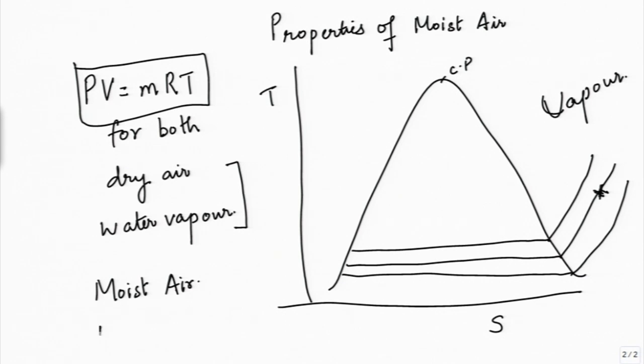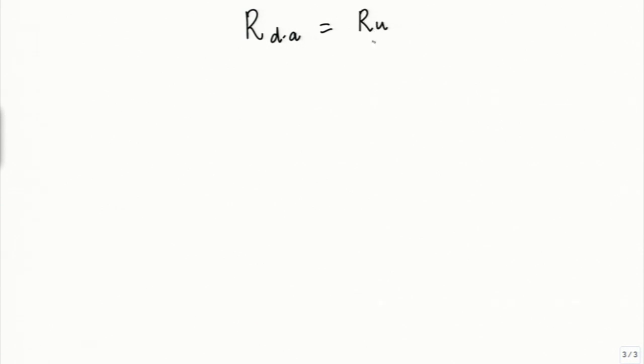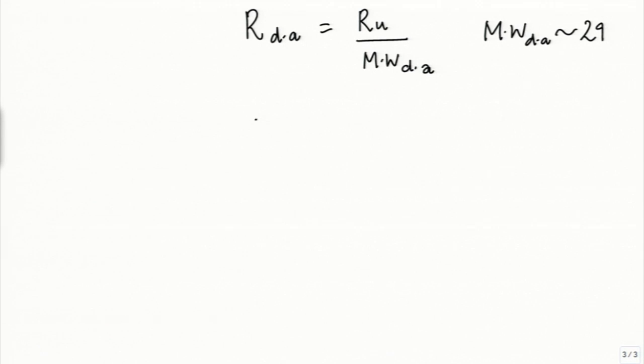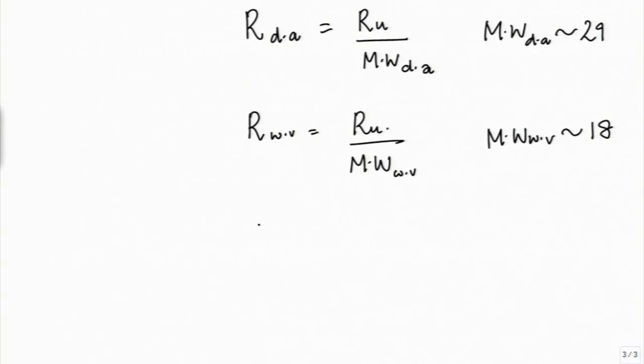Both dry air and water vapor together constitute moist air, and we can think of both as ideal gases and apply the ideal gas equation to each. The specific gas constant R will be different for air — call it R_dry_air — and different for water vapor — call it R_water_vapor. R for dry air is the universal gas constant divided by the molecular weight of dry air, approximately 29. R for water vapor uses molecular weight of water, approximately 18, since water is H₂O — two hydrogens and one oxygen.